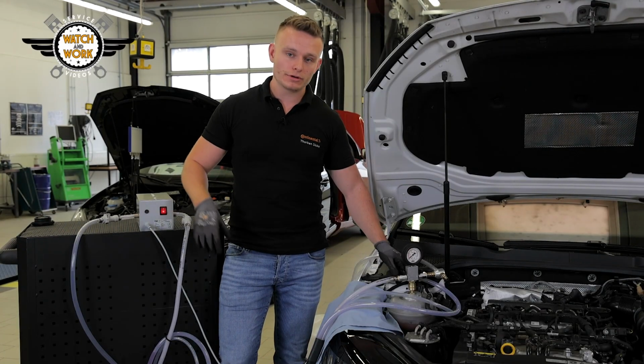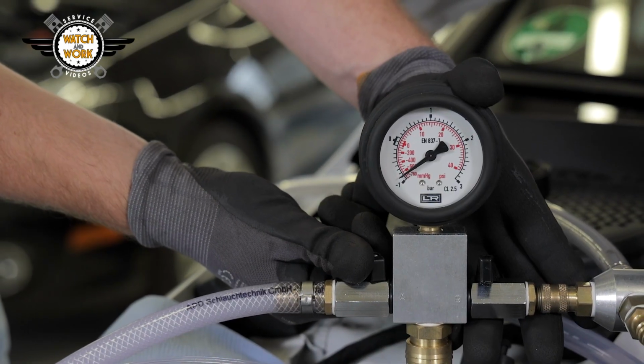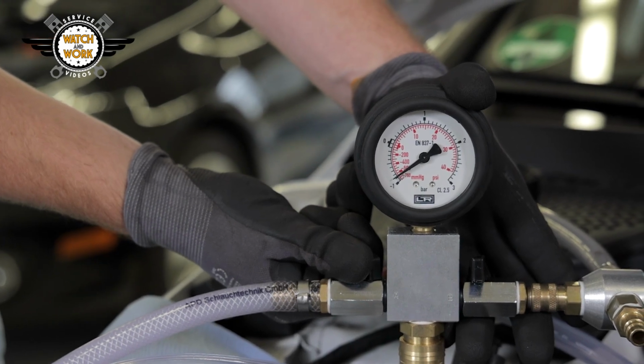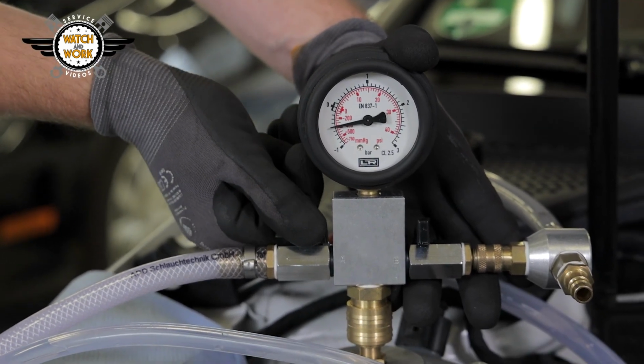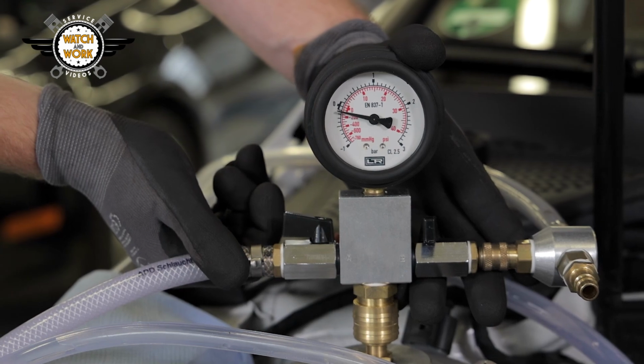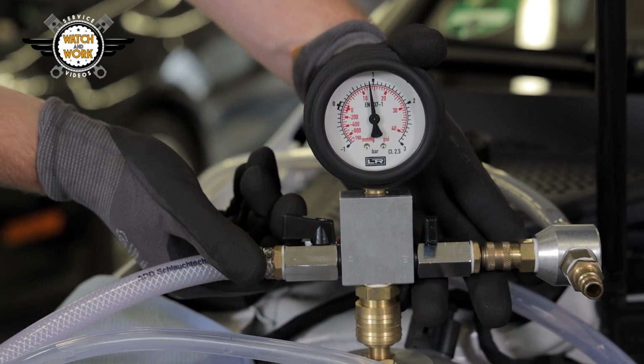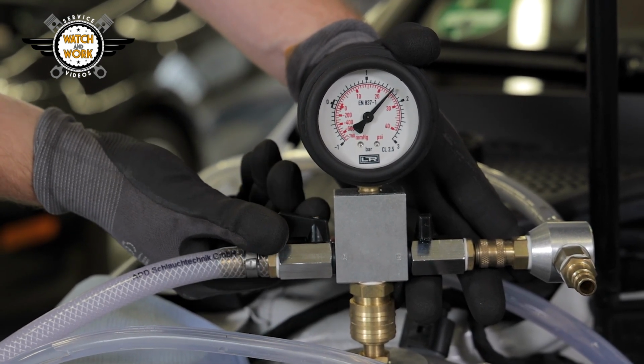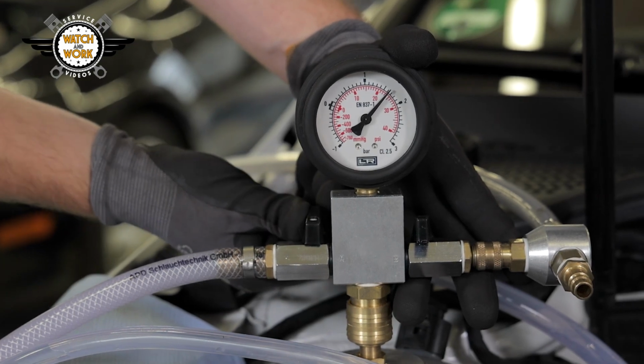With the pump switched on, we slowly open stopcock A. Distilled water starts to fill the cooling system due to the vacuum inside it. The pump automatically supplies distilled water and switches off as soon as the cooling system is full. You then close stopcock A again.